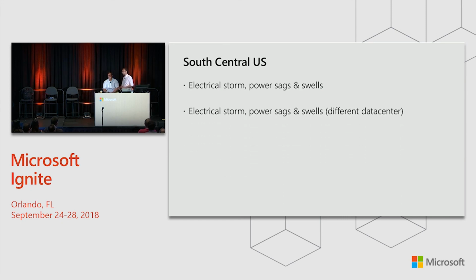Unfortunately, 30 minutes later, the exact same thing happened at another data center within the region, and this time, the outcome was slightly different. Once again, a major sag came in, it lost utility power, and it locked out our chiller plant. At the same time, the thing that made this a little bit different is that multiple other events started triggering. Generator power started spinning up in areas, although we didn't fail utility power, and there were other events occurring.